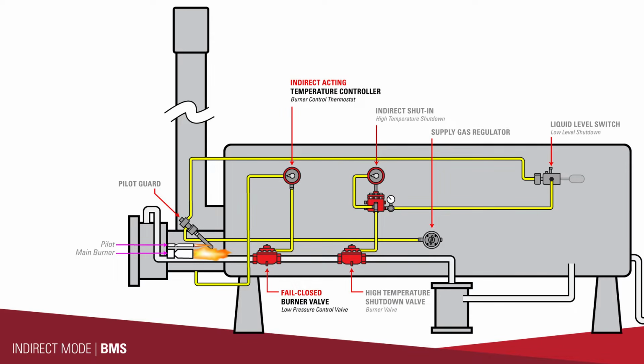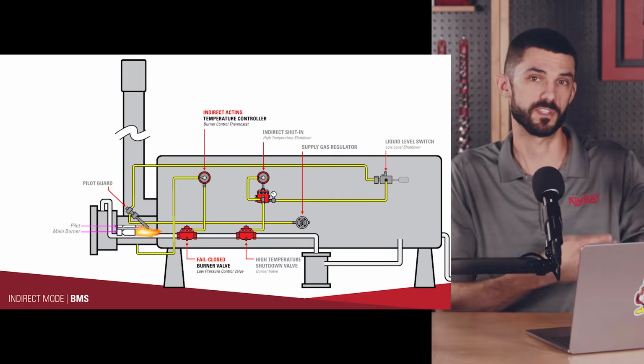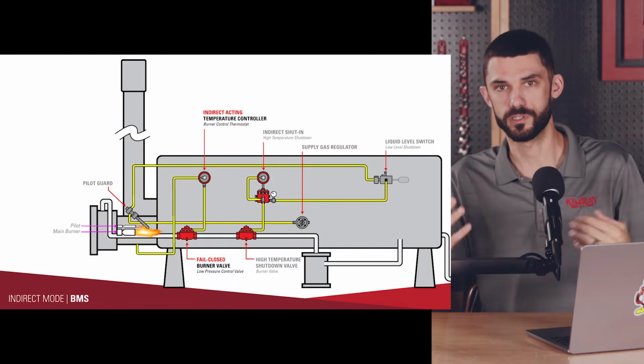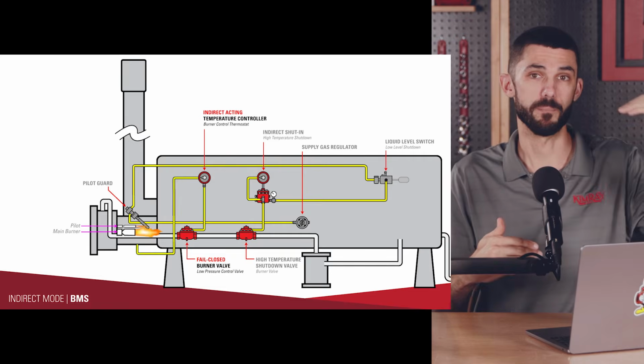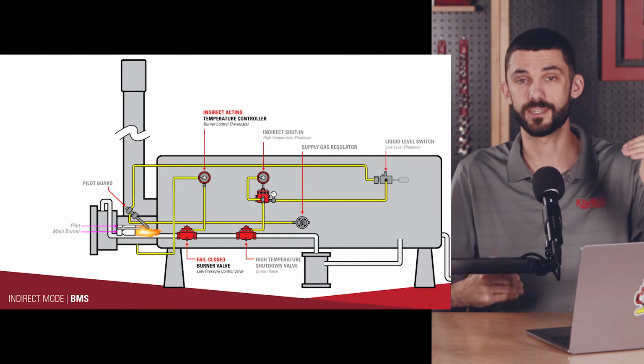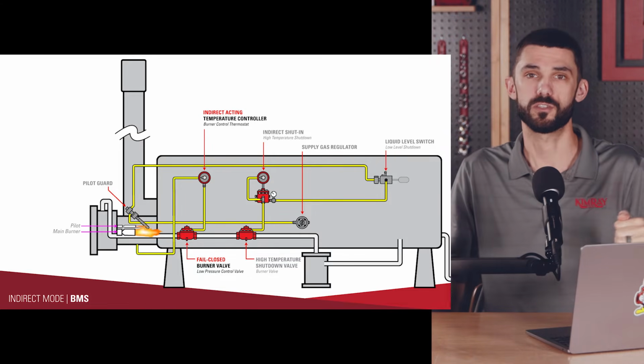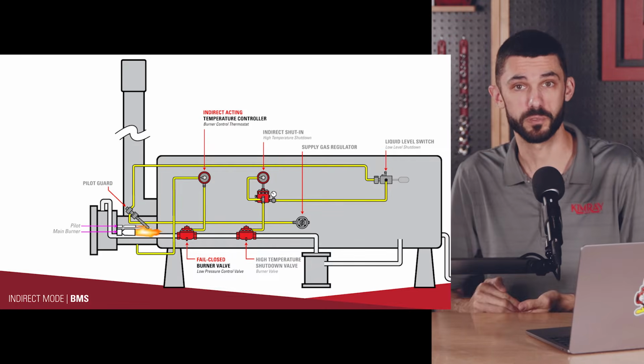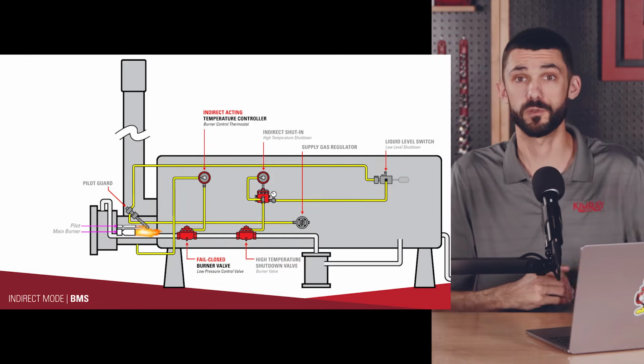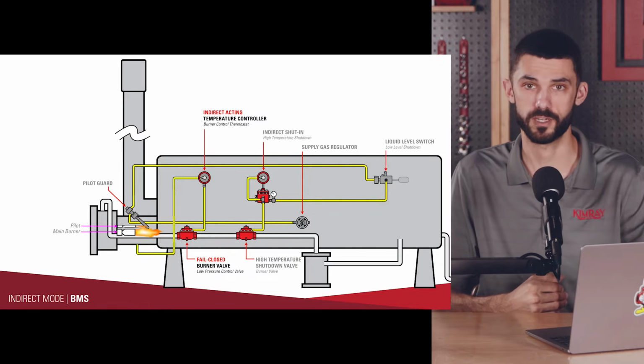Most typically, the burner valves that the temperature controllers are going to be operating are going to be fail-closed valves. And so in that scenario, you want an indirect acting temperature controller. So when you have a rise in temperature above your set point, that means you want to close that burner valve. If it's a fail-closed valve, or pressure open is another way you could say that, when you have a rise above your set point, that controller will be venting that signal that's holding that burner valve open. And so that will cause the burner valve to go to its failure position, which is closed, closing off the path for fuel to get to the burner. So that will start cooling the temperature back down.